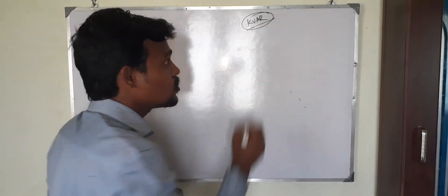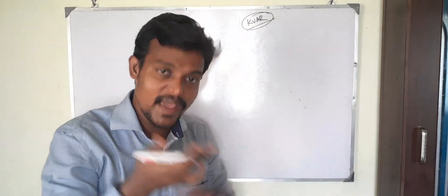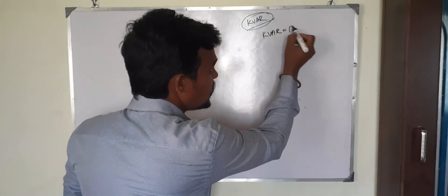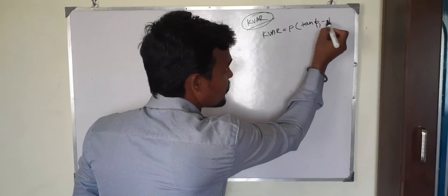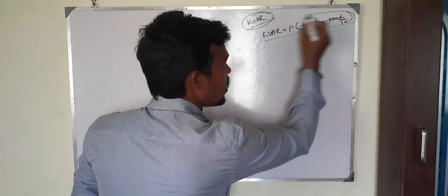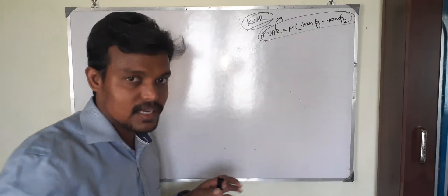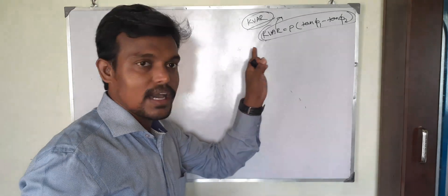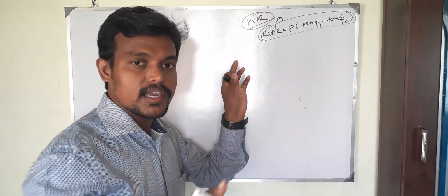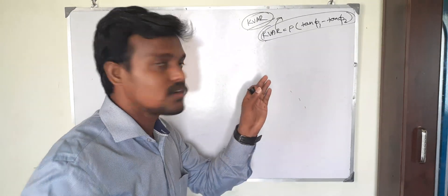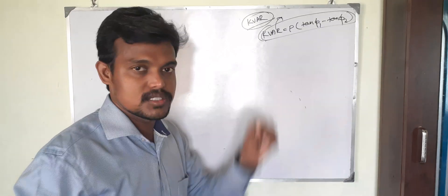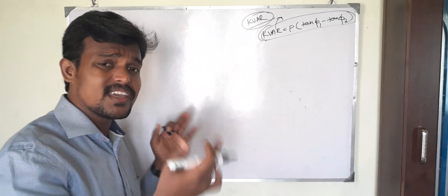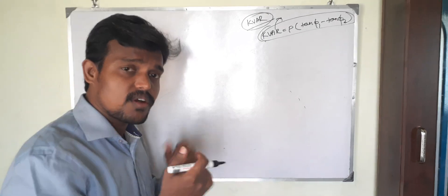Regarding APFC, how do we calculate the KVAR? I have already done a video on this. The formula is: KVAR = P × (tan φ1 − tan φ2). I explained how to calculate the KVAR based on your maximum load very clearly in my last video, which is available in three languages. The link is in the video description.